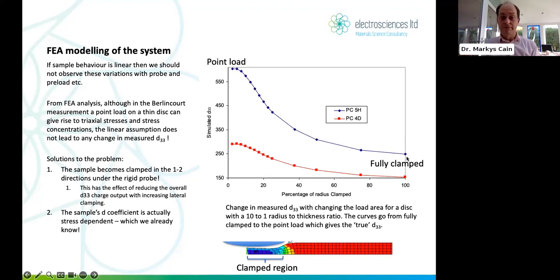Now, in the Berlincourt method, we're somewhere here. We're not over here. We're not putting a great big flat plate on the sample, but we're somewhere here, which means we have so many things going on. We are clamping the X and Y direction that the sample wants to move when it moves up and down under stress, by virtue of the geometry of the probe. Geometry of the probe, which is why we suggest not using flat probes or flat punches, and why we suggest also using small diameter electrodes.